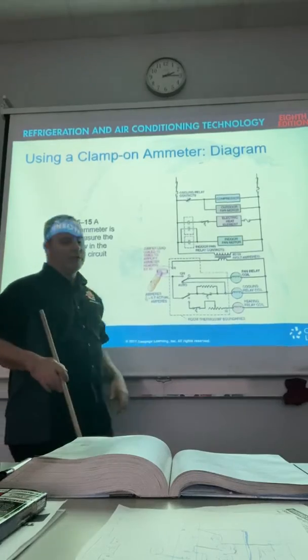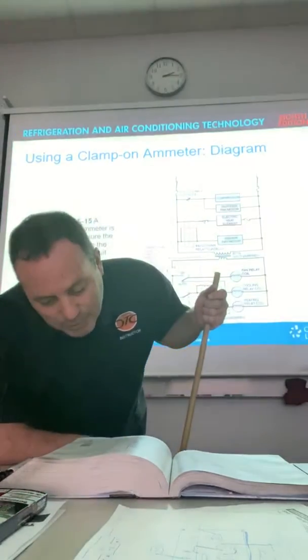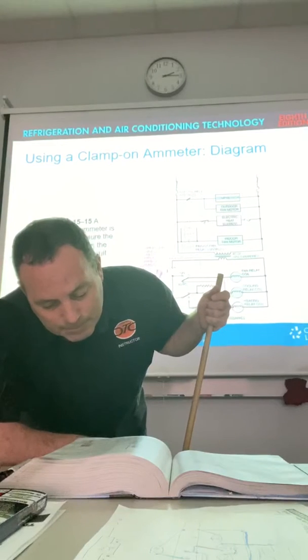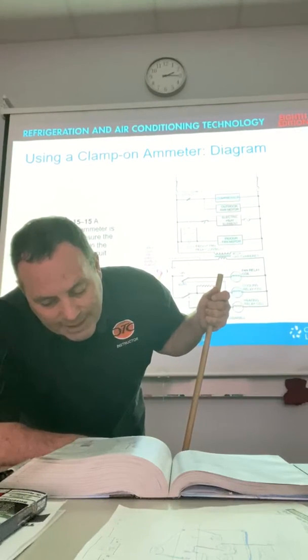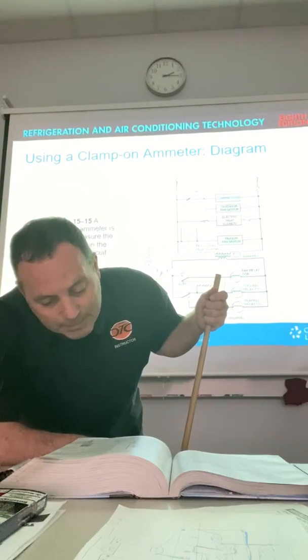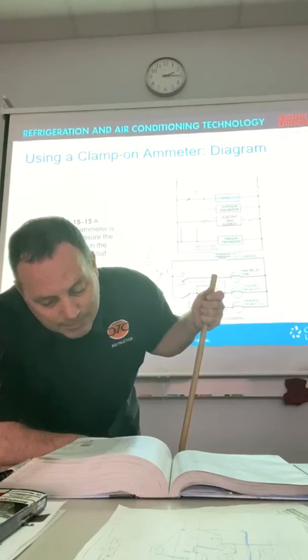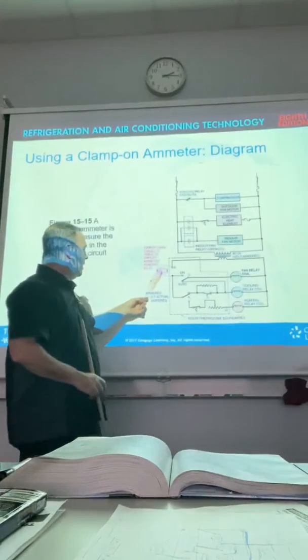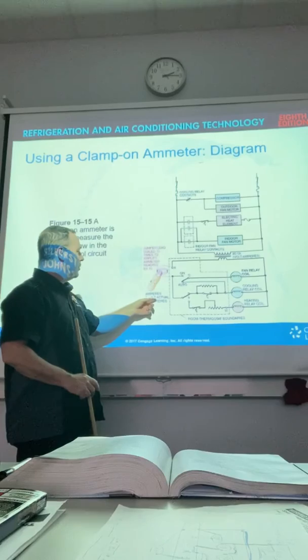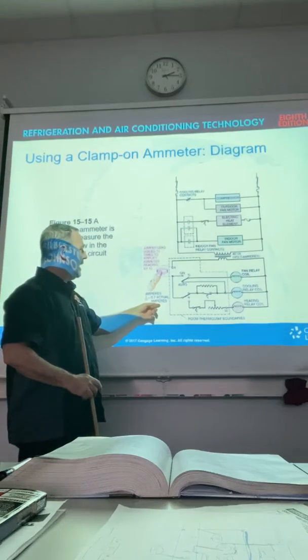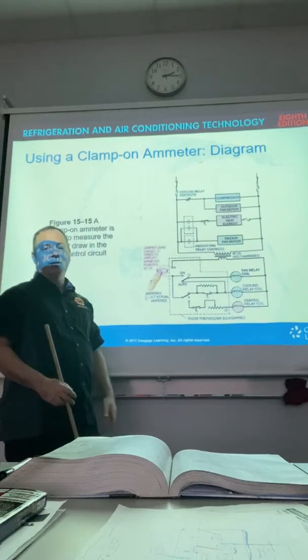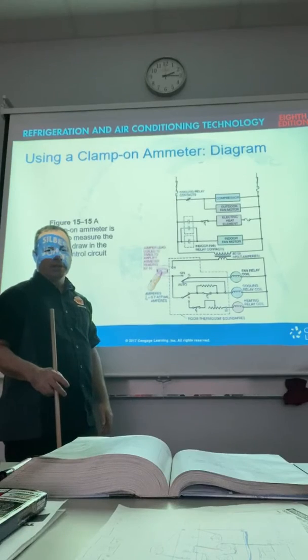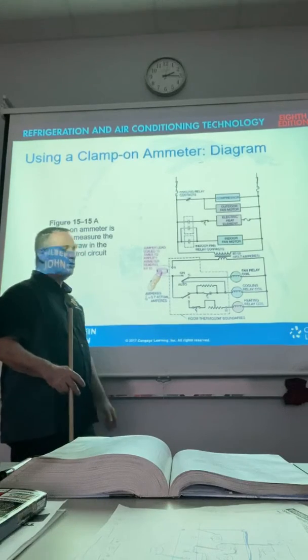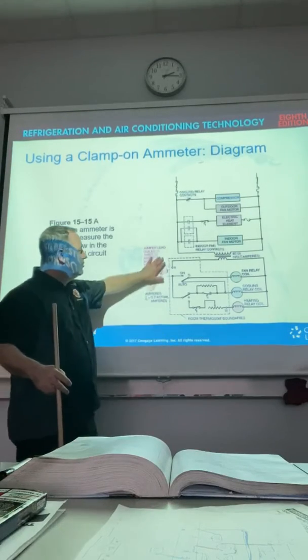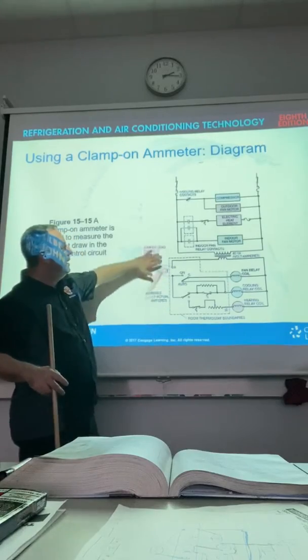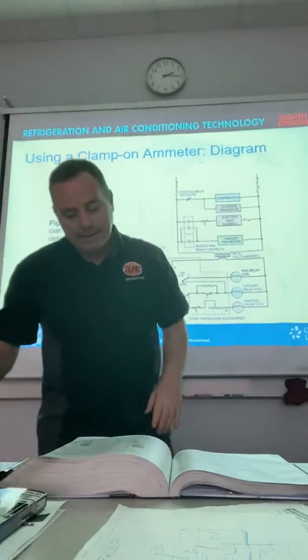Okay, whatever it says. Now your book says in this example, let's say it was drawing 7 amps. Well, you divide it by 10, the number of times you wrapped it, and now you have 7/10 or 0.7 actual amps. Well, that'll work with the 1.66 amp transformer because it's only drawing 0.7 amps. So that's how you would work that.